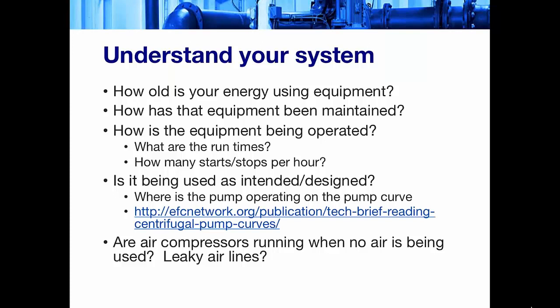If you do not know where you're operating at on your pump curve, or you need a refresher on how to read a pump curve, or pump curves look like Greek to you, then I would highly recommend that you take a look at this tech brief. It's very straightforward and explains reading pump curves quite nicely. So if you're not operating on your pump curve the way it was intended or designed to be used, chances are that pump is not being used efficiently as far as its energy consumption. So make sure that you understand your system, your pumps, and how they were intended to be used.